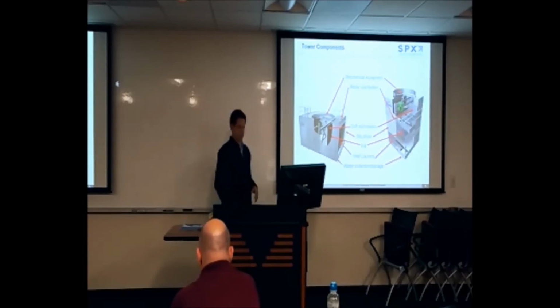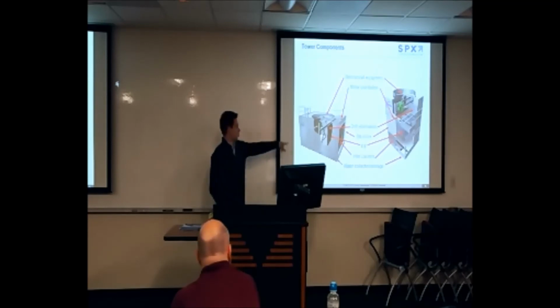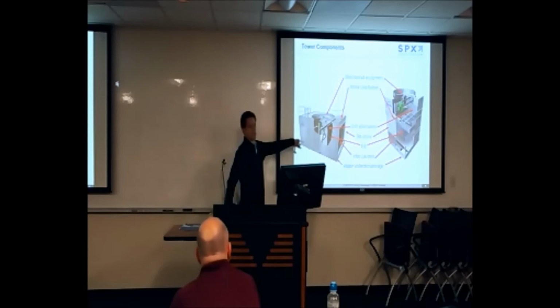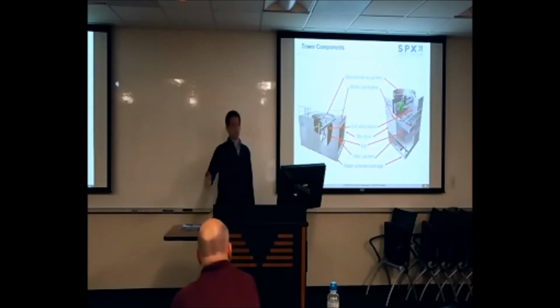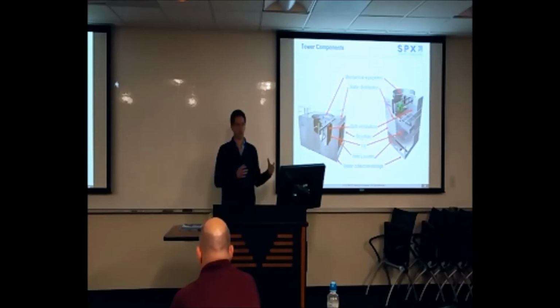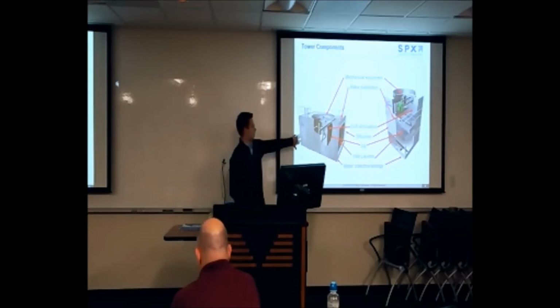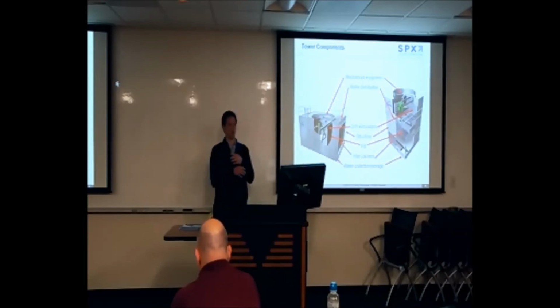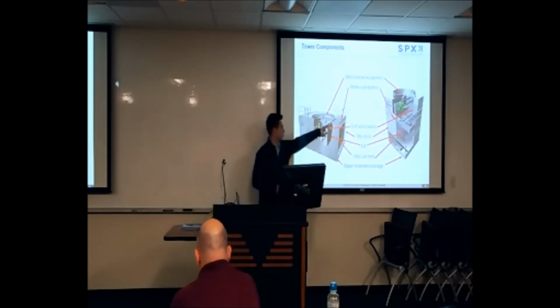So real quickly, the towers specifically that you guys received recently was this cross-flow tower on the left. As Aaron mentioned, you have an open cooling tower, and within open cooling towers you have cross-flow towers and counterflow towers. So cross-flow is this one on the left. That is when the air is traveling across the direction of the water. I'll explain this in the components, but water is falling down the tower and air is traveling across the direction of the water travel.